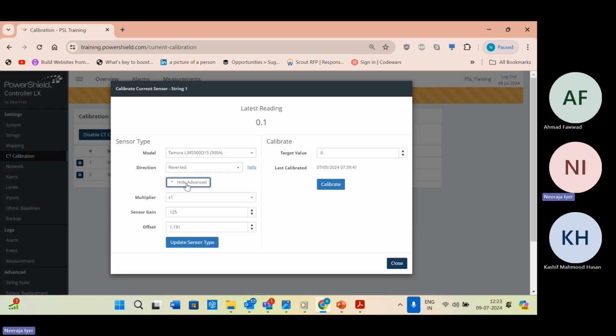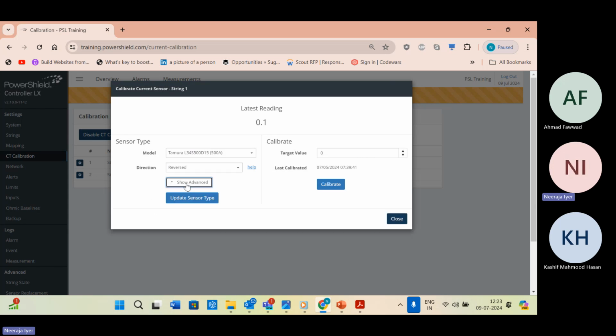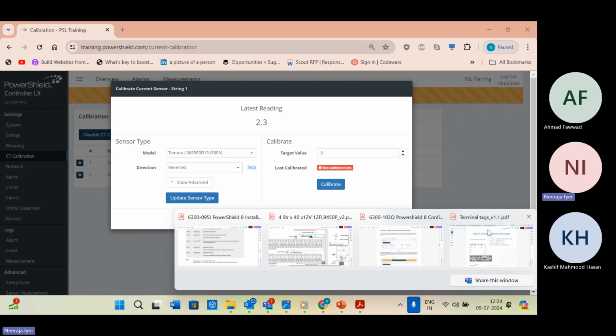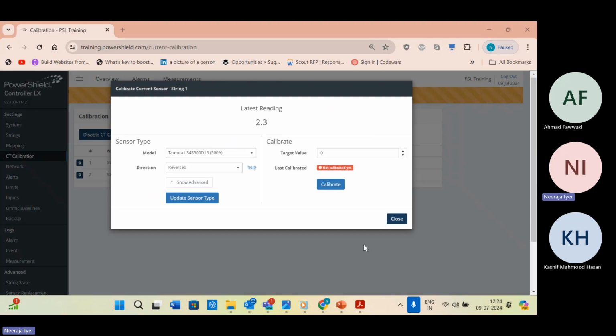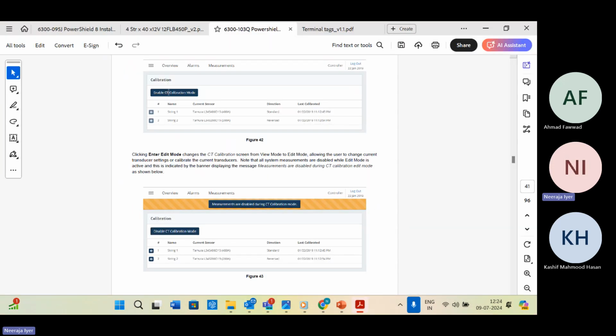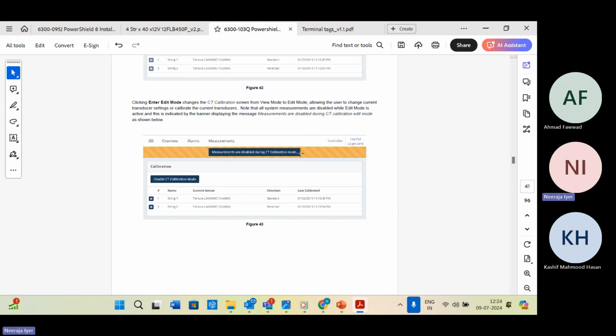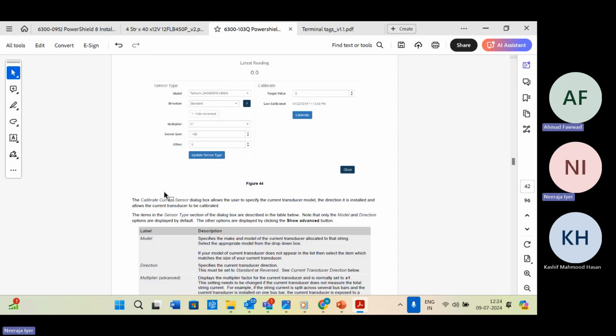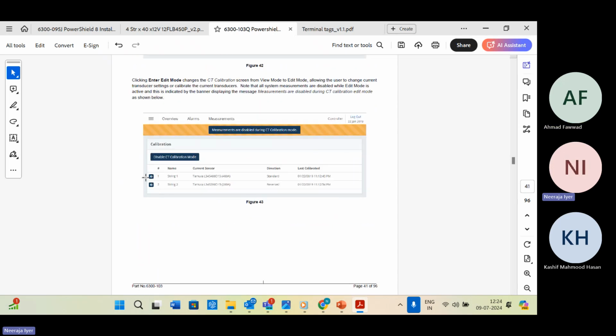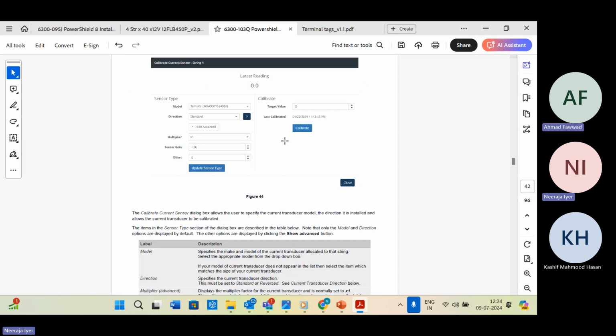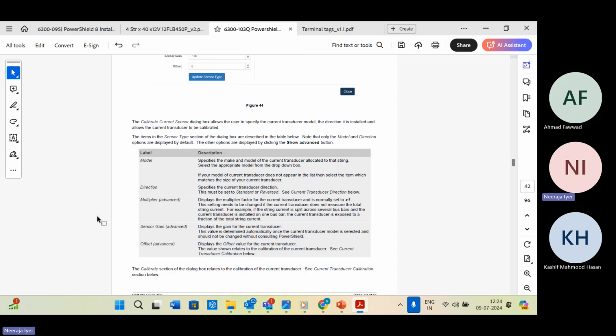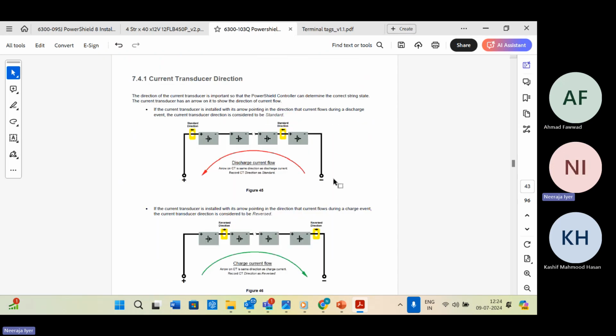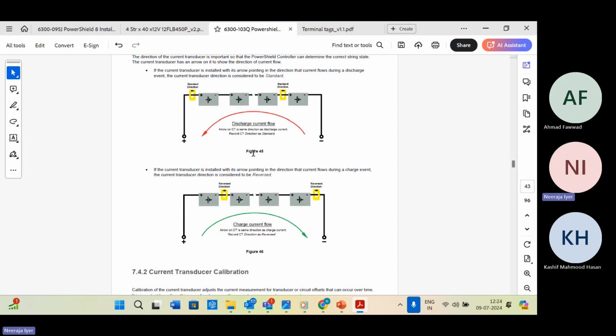And this advanced option is just the gain of the CT, which is default. That's fine. Just make sure you click on update sensor type. Now, this is where the calibration comes in. I'll just quickly jump into the manual. Like it is mentioned, you click on enable CT calibration. An orange ribbon comes. You click on the settings button. And this is the sensor type. Whatever the direction of the CT is, it's given here as well.